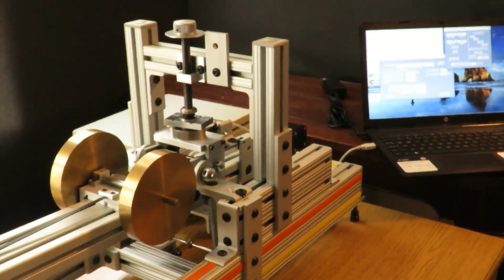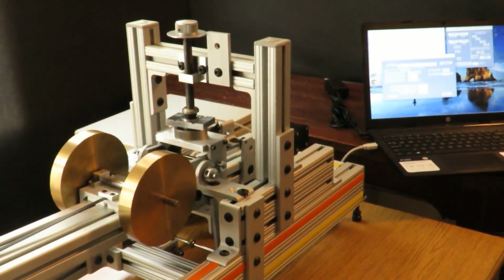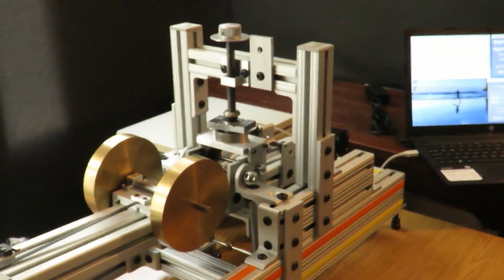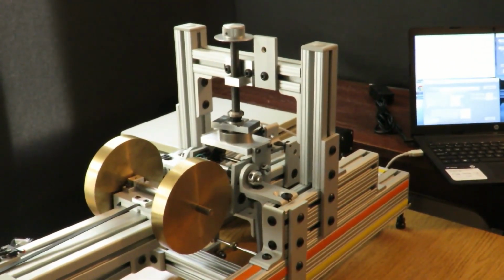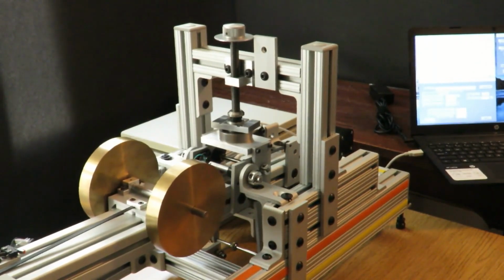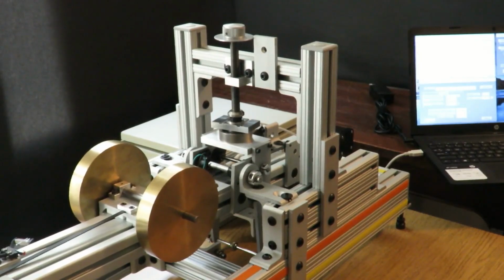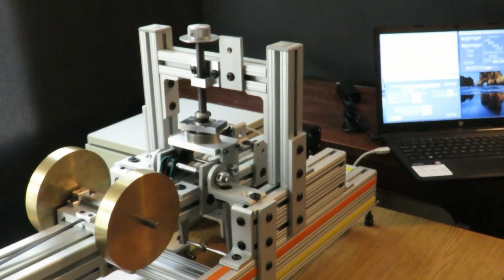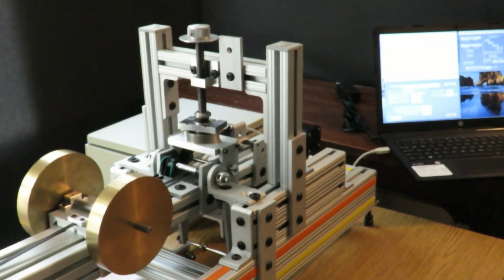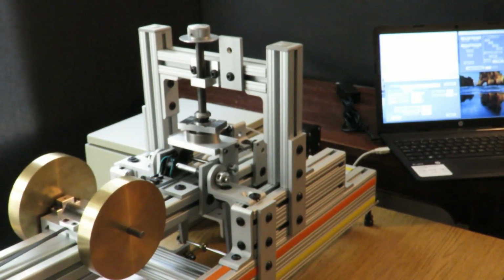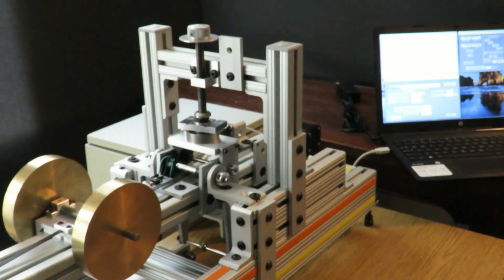As we initialize, the test starts. Moving table moves with weights on it and stops at every half inch. When it hits the limit of 10 inches or 40% or 120 pound force strain, it reverses.